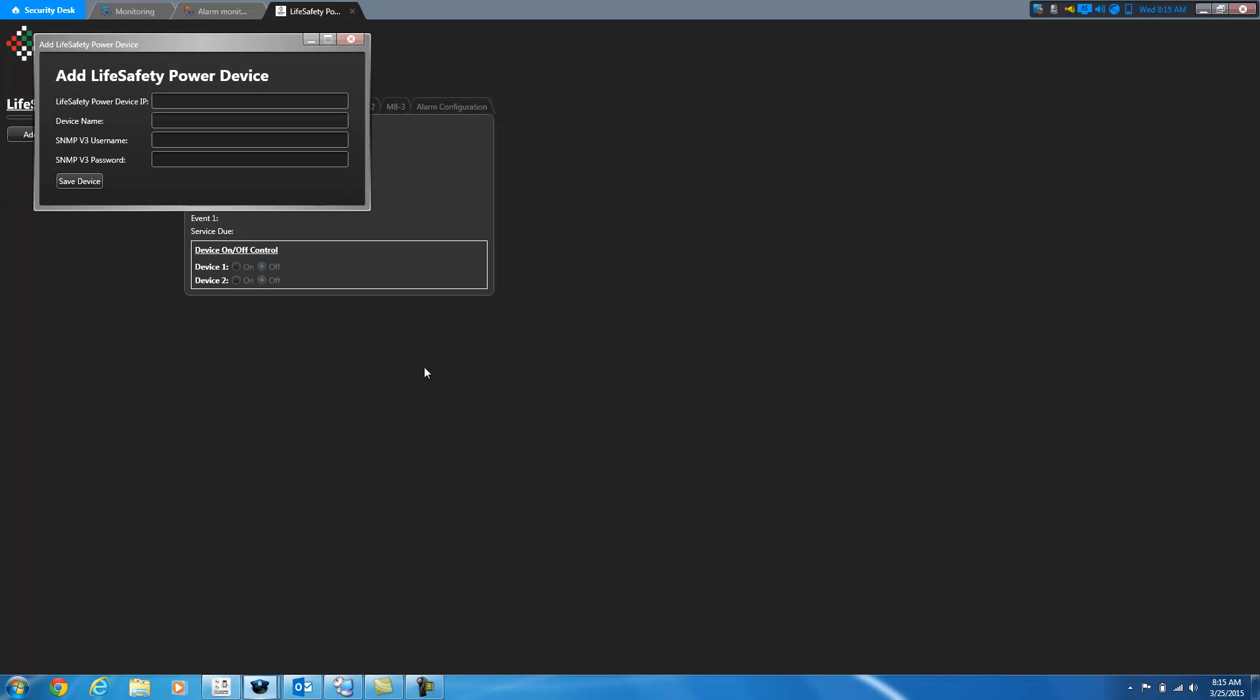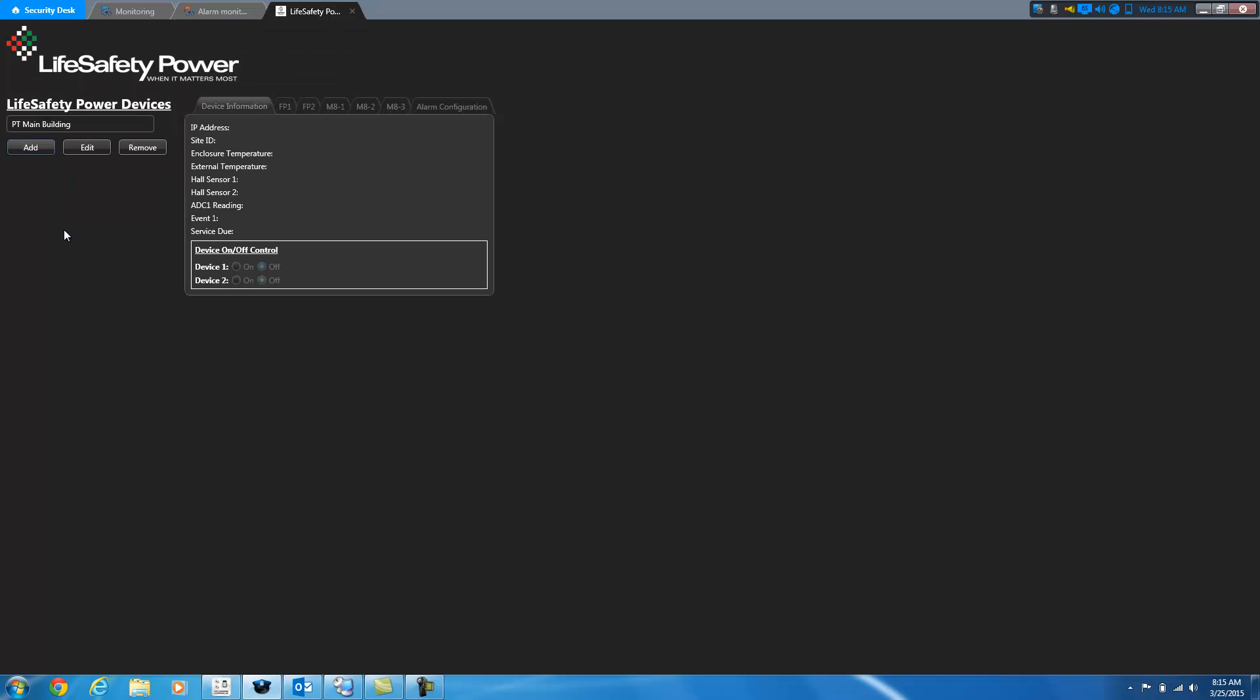So I'm going to go ahead and add a device. So I click add device and then I put in the IP address of the device and then give it a name. I'm going to call this PrefTech Main Building. And then it connects to the device via the SNMP protocol. And we're using version 3 so you'll need to provide a username and a password that you would have set up on the device when you were configuring it initially. And then we'll click save and I've added the device.